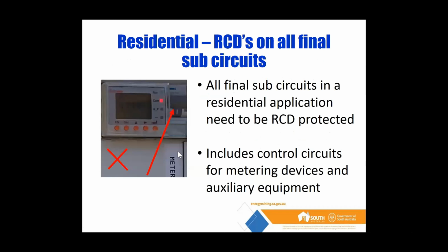Another thing that we commonly find is guys installing things inside of a switchboard. Now, again, this is an example of a solar battery type meter arrangement, but it can be taken into account for a number of other things. It could be an irrigation control, it could be a monitoring device, it could be some lighting control for tennis court lights with a contactor. There's many different things in there that you require an RCD for.